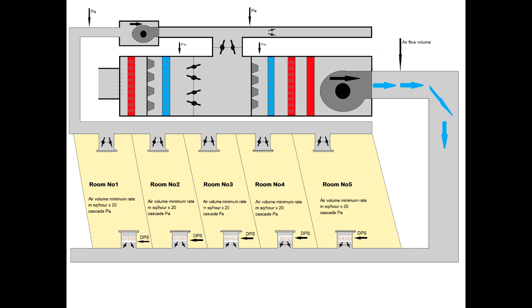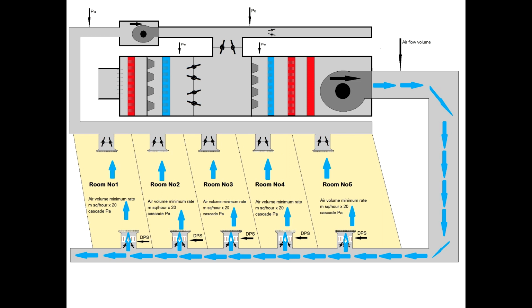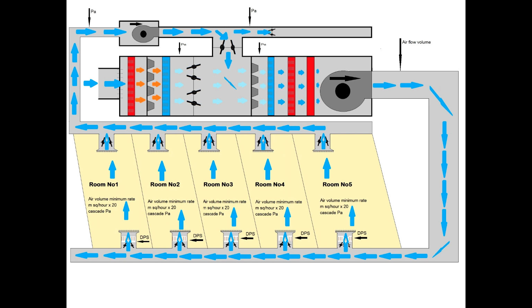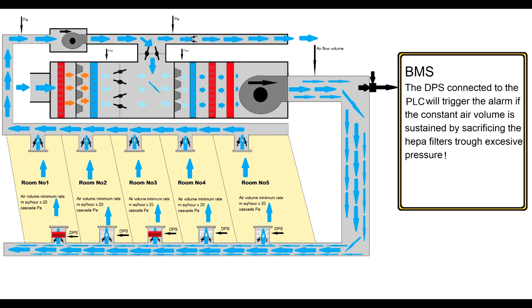Now let's talk a little bit about the HEPA filters, because this AHU provides filtration through some normal filters, but again, it's a special environment. So every AHU duct, every outlet, is provided with HEPA filters. The HEPA filters retain 99.97% of little particles that pass through an ordinary filter. So while the air passes the way you see, it's recirculating through the system, brought back into the mixing chamber, meeting with the fresh air, coming back. As long as the filters are okay, it's all good.